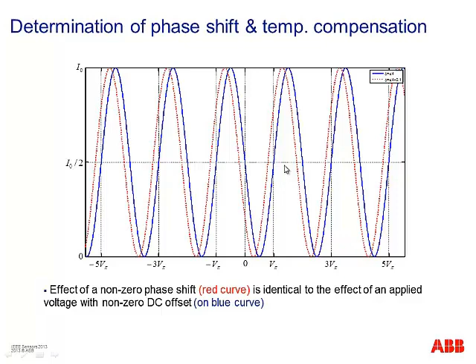And we can observe that the effect of this is exactly the same as the effect that we would have if, instead of applying a perfect AC voltage without any offset to the blue curve, we would apply an AC voltage with a DC offset. So this observation can be used because in actual applications, in substations or in the power grid, you don't have a DC offset, or at least you don't have it for long. It could happen in some transient conditions that you want to measure, but in the mean, the DC component is 0. Therefore, if in your reconstructed signal, in the voltage that you reconstruct according to what I said before, you observe a DC offset, then you know that this DC offset will be due to the quarter wave plate.